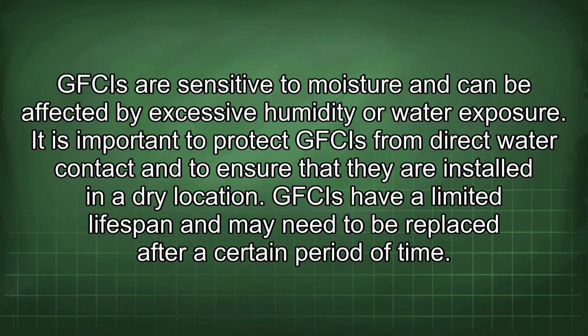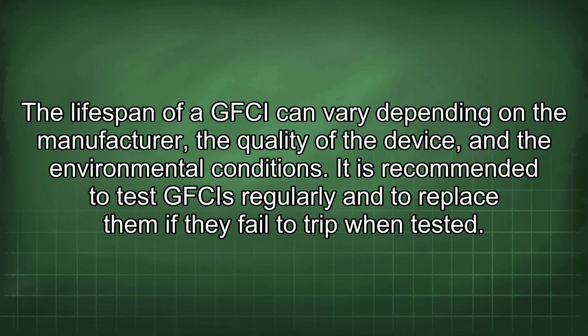GFCIs are sensitive to moisture and can be affected by excessive humidity or water exposure. It is important to protect GFCIs from direct water contact and to ensure that they are installed in a dry location. GFCIs have a limited lifespan and may need to be replaced after a certain period of time. The lifespan of a GFCI can vary depending on the manufacturer, the quality of the device, and the environmental conditions. It is recommended to test GFCIs regularly and to replace them if they fail to trip when tested.